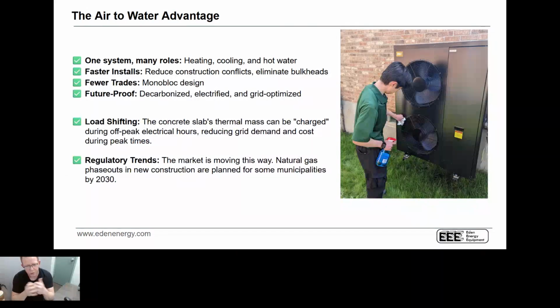And we're going to talk about that, as well as different ways that we can do heating and cooling inside of the space. So, the air-to-water advantage, we talked about this before. It's one system with many roles. It does heating, cooling, and it also does hot water, which is great. The other thing that's really good about it is because it's a monoblock design, it also allows for faster installations. It's going to reduce my construction installation time.